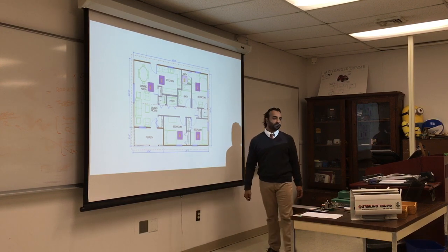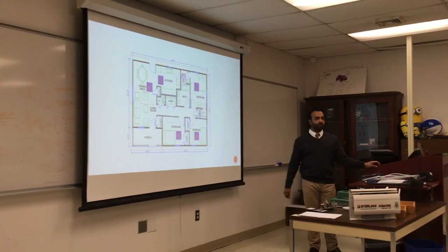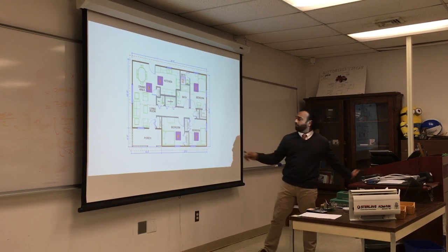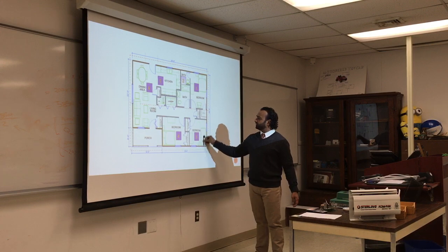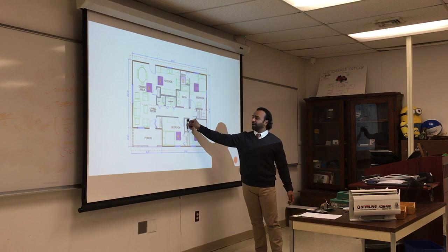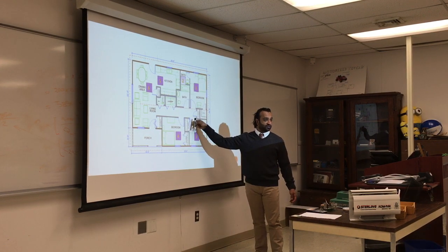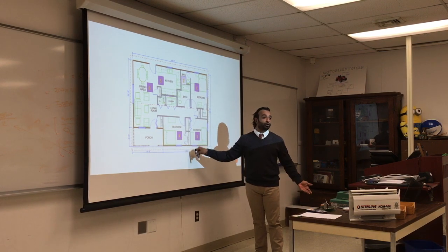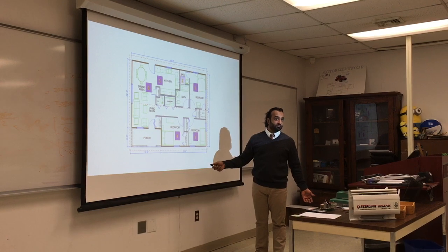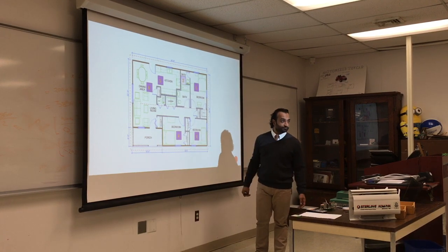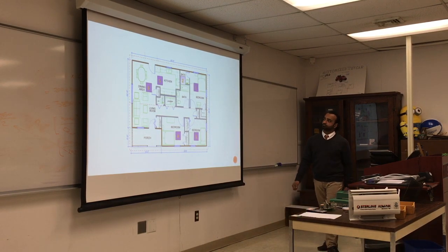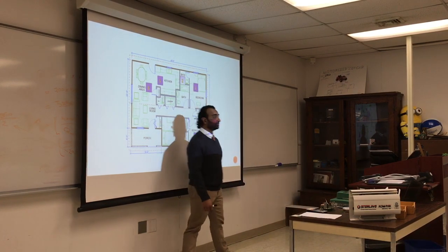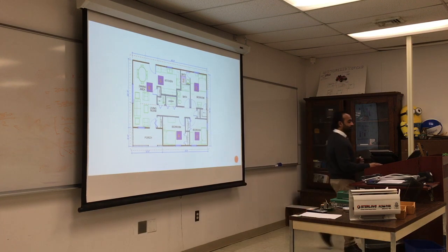So you have to exclude it? Yeah. When you do the infiltration, you're going to calculate the volume, right? But it's not going to be the volume of the closet, it's going to be the volume of the bedroom. The closet's going to be half full with clothes and stuff, so the volume is very insignificant. So you should not include it. If you include it, it's not going to be a big deal, but you don't have to. Right, and you said don't do the porch either, right? Not unless you want to heat the porch, but this is all glass, it's going to cost you a lot of money to heat it. Okay?